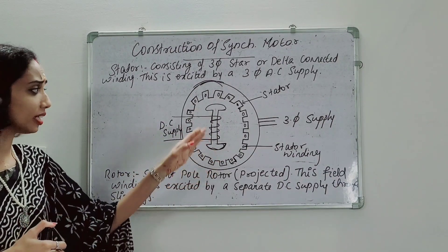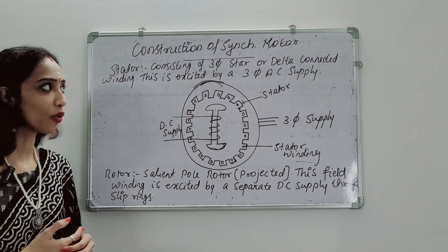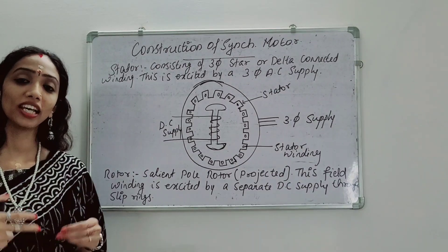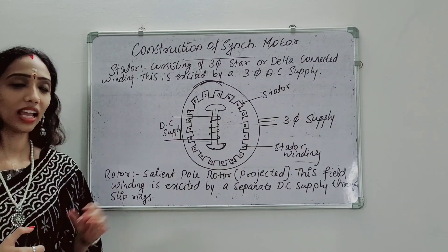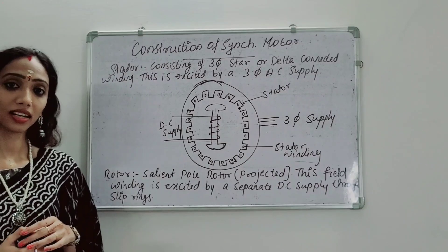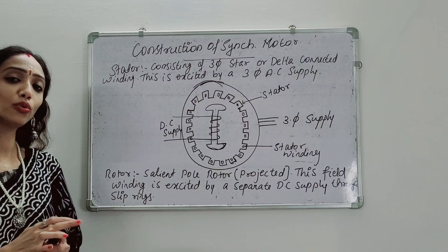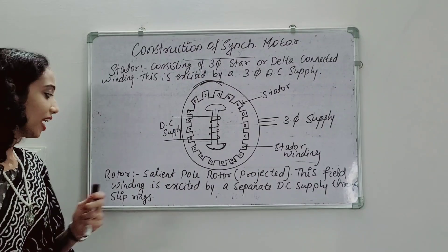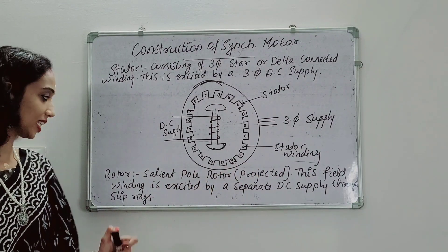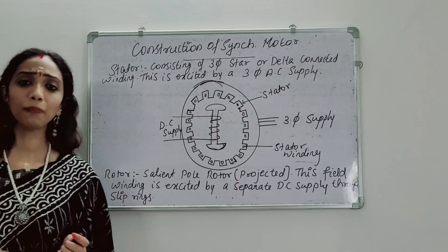Now, we rotate this rotor with excitation provided. In summary, the construction of a Synchronous Motor: these machines are similar to the Alternator. It consists of two main parts — the Stator and the Rotor. The Stator has a 3-phase star-connected or delta-connected winding with 3-phase excitation. The Rotor is a Salient Pole type, and this field winding is excited by a separate DC supply through the slip ring.